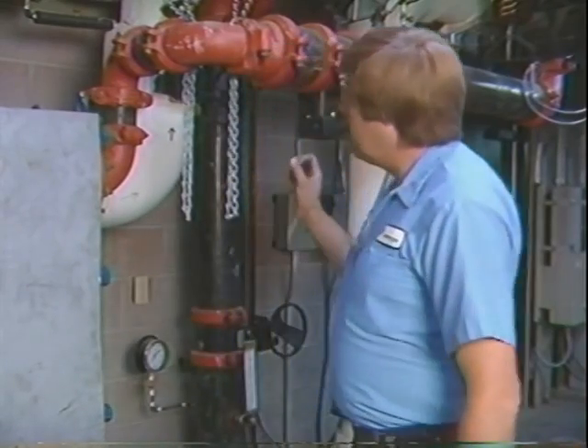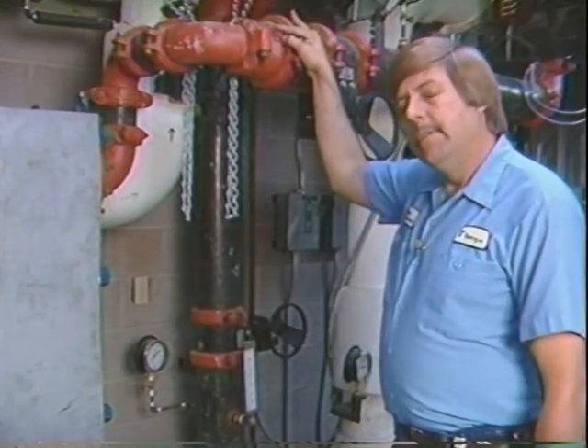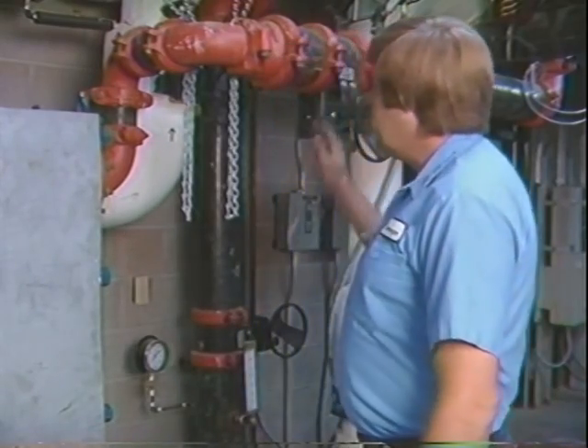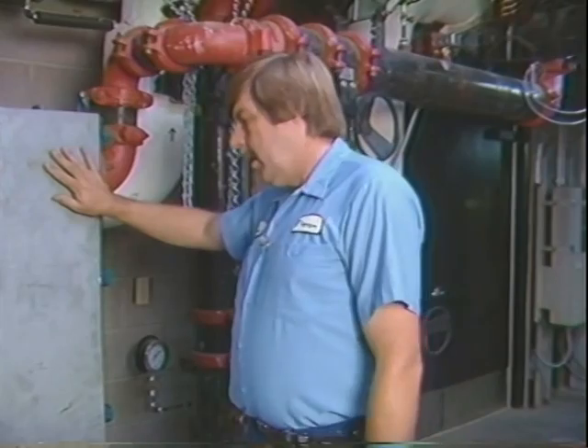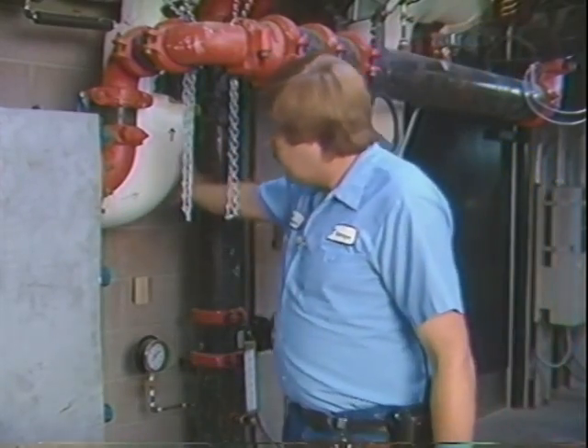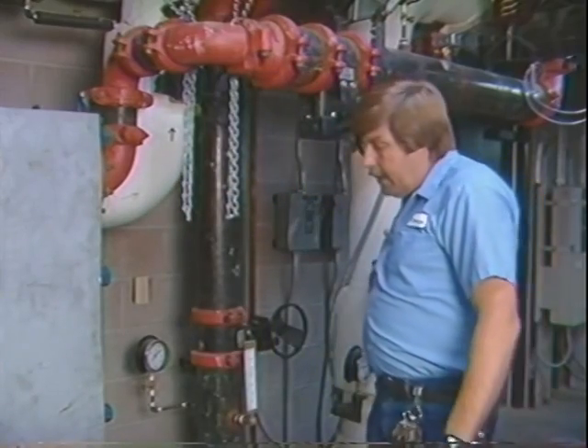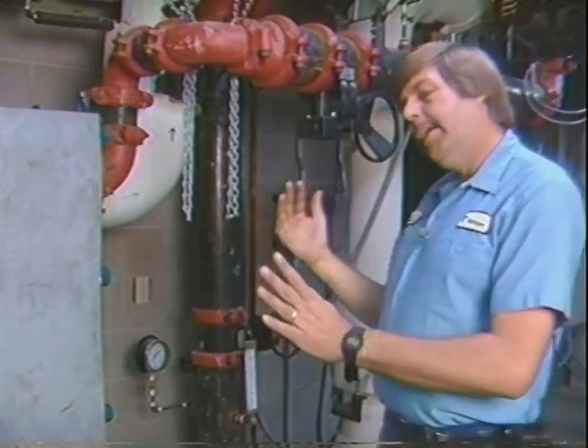This heat exchanger, which is very similar to the one that we have in our police courts building, is used to take water from our cooling tower. It's circulated through this heat exchanger in those times of the year that we can get cold enough tower water, in the cases of low humidity and lower ambient temperatures. We can get that chilled water. It goes through this exchanger and it cools the building water supply, which comes through these lines here. It's exchanging the heat between the tower water and the building water, cooling the building water so that we can maintain the building without having to run the chiller system.